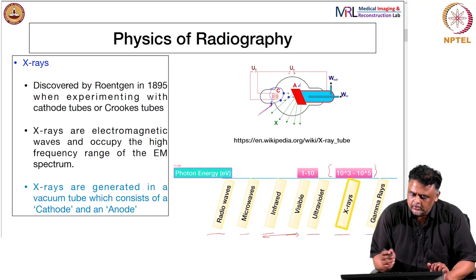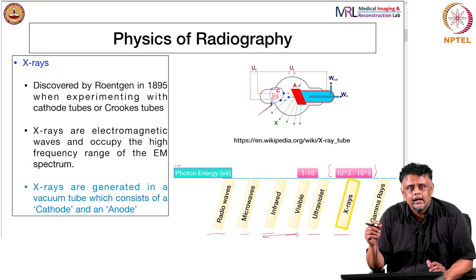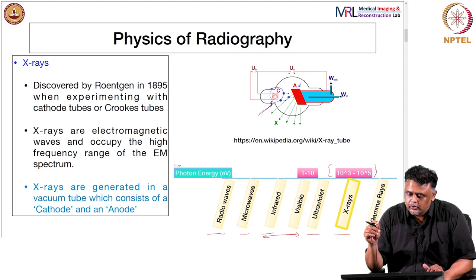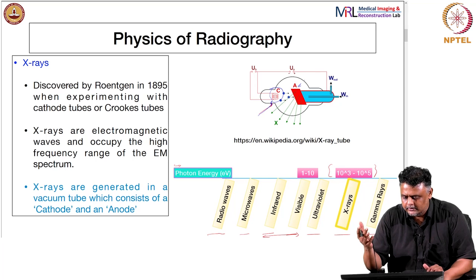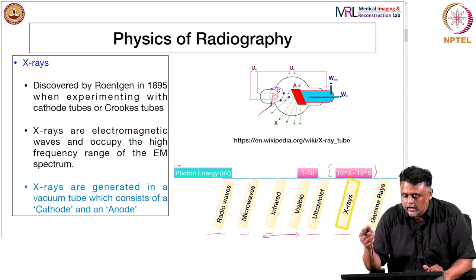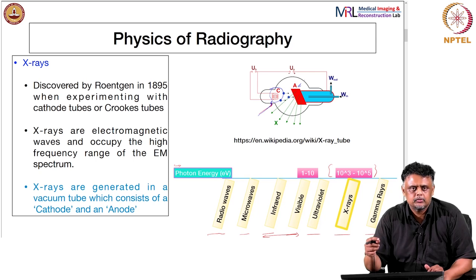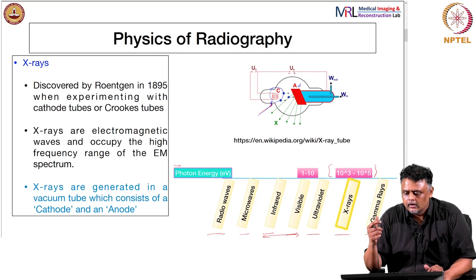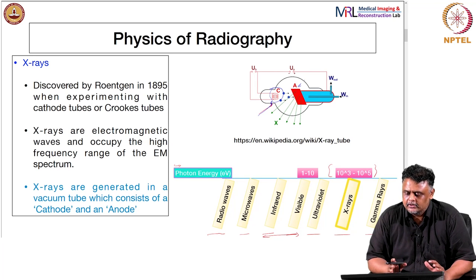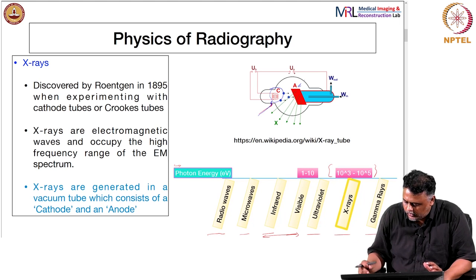All electrons emitted by the cathode are accelerated and focused to hit a spot on the anode target. The size of this spot has an impact on the resolution of the final image. In many reconstruction techniques, the idealization is made that x-rays come from a point source, but this is not strictly true. For a clinical x-ray tube, the spot size is of the order of 0.2 to 0.5 millimeters. This is a qualitative look at these imaging systems.